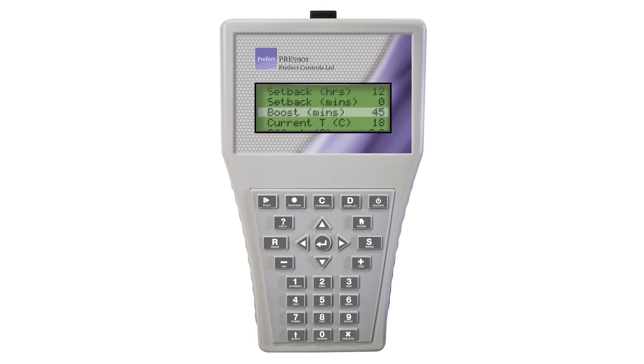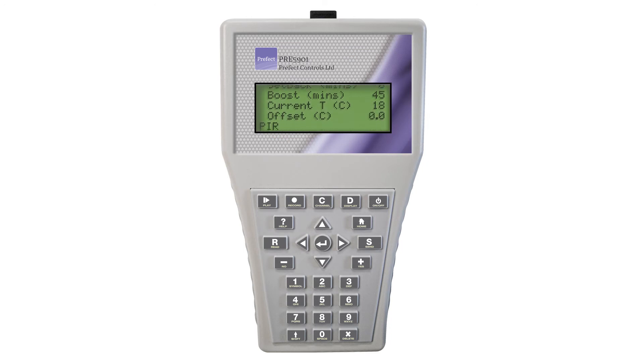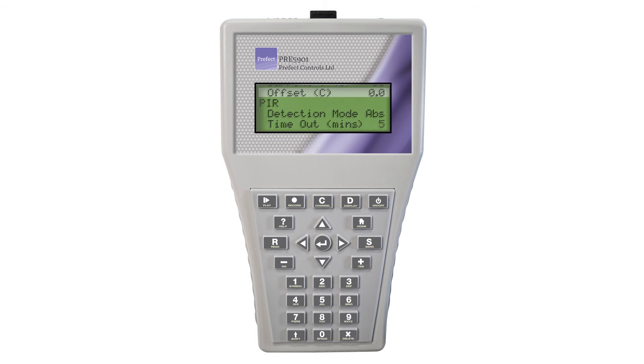Boost mode is set in minutes only. This is the amount of time the temperature will remain at the boost level before reverting to setback mode. Current temperature is only active if you have read the thermostat — the temperature the thermostat is currently experiencing will be displayed. Offset can be programmed so that the heater output is a few degrees higher or lower than the actual temperature. This is useful if the thermostat is on a cold wall or in close proximity to the heater, as in these circumstances thermostat readings are not a true representation of the room. The offset has increments of 0.1 degrees C — use the plus or minus buttons to offset the thermostat.